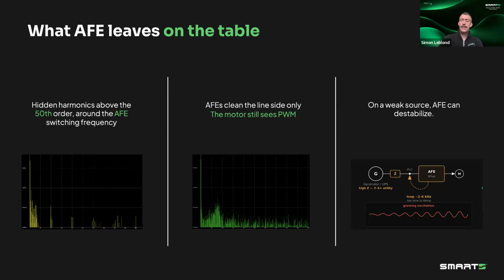Now, the second thing. Harmonics also exist on the motor, and all of the solutions we've looked at, including AFEs, only look at the grid side. You can see it's interesting here: the motor side harmonic signature is much more dispersed, because it's really noise from that high frequency switching. So all of your AFEs are causing those harmonics on the motor side. They're causing the other issues I've talked about before, the dV/dt and the common mode current, and many active front ends actually have higher common mode current than standard drives. So they're potentially amplifying the issue on the motor side of bearing fluting and early failures.